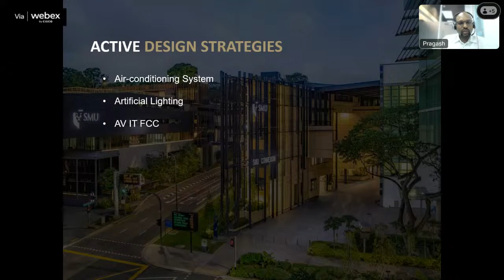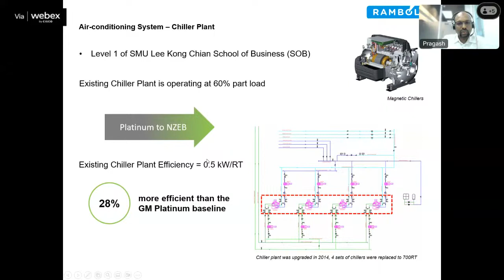More importantly, this project is very unique, and the innovative design feature is the air conditioning system, how we designed the air distribution system. Before that, we reduced the cooling load of the building as much as possible by optimizing the passive design. This helps us tap chilled water from the existing chiller plant, which is also very efficient at 0.5 kilowatt per RT, while the benchmark in Singapore is about 0.7 kilowatt per RT.